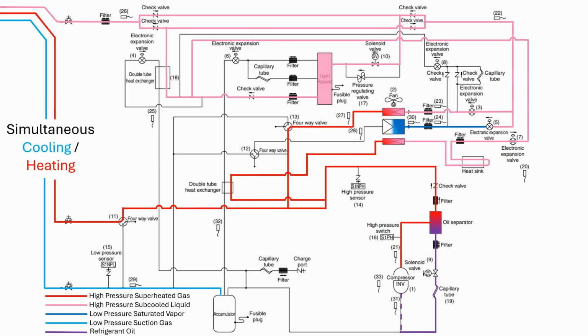The saturated vapor refrigerant is passing through the outdoor heat exchanger, collecting heat from the outdoor air, and superheating the refrigerant into a suction gas. The suction gas leaving the outdoor heat exchanger is routed through a four-way valve and meets up with the suction gas returning from the indoor units just ahead of the accumulator. The suction gas leaving the accumulator is routed back to the compressor to start the process over again.